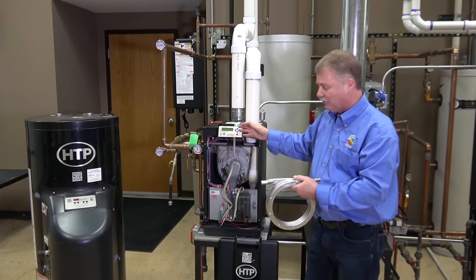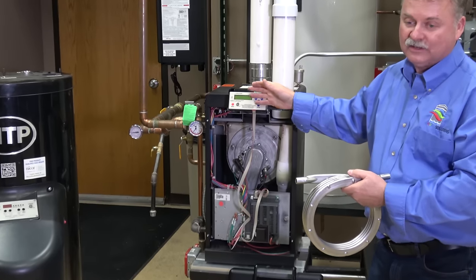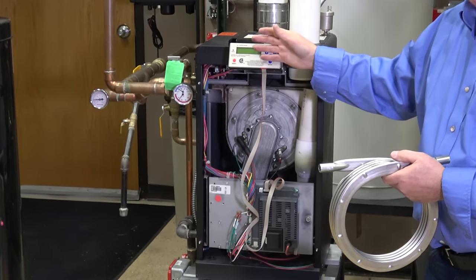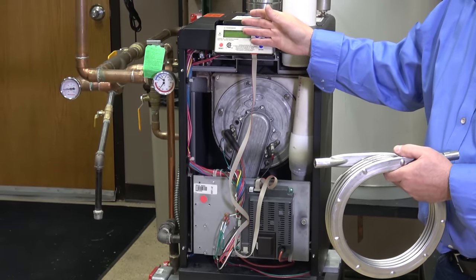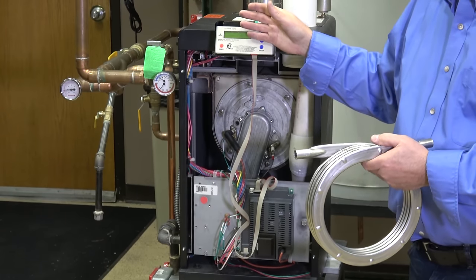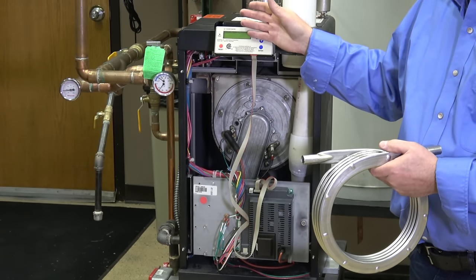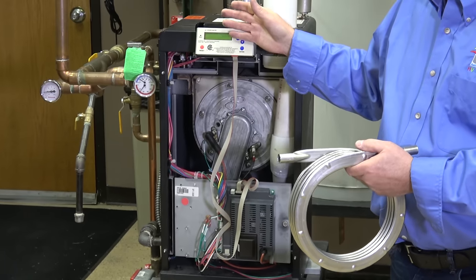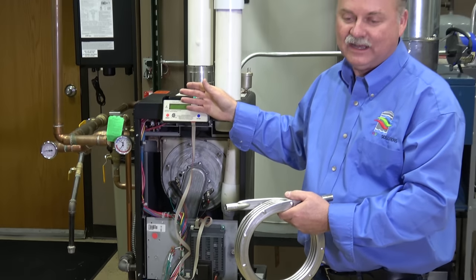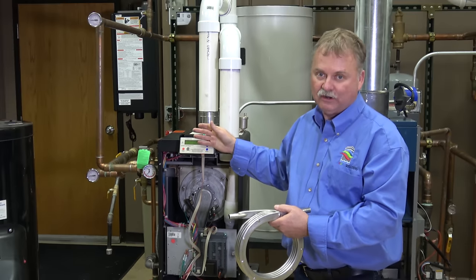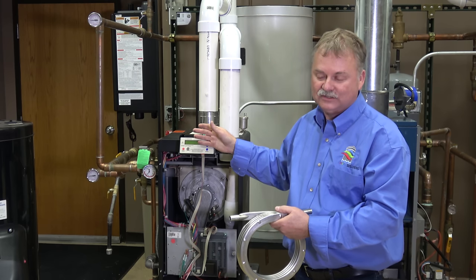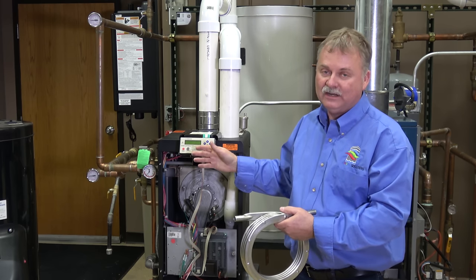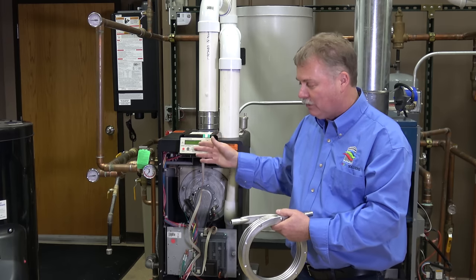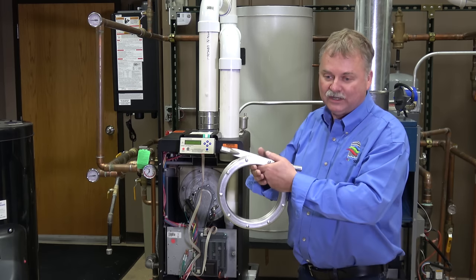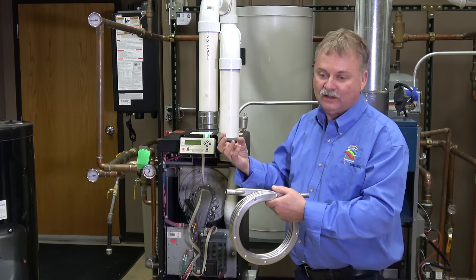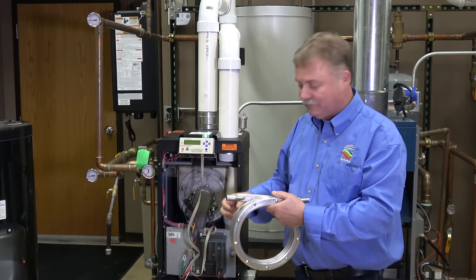A little bit different, you see a lot more controls here. It's basically a lot of readouts, a lot of stuff going on. There's a lot of programming. All these high efficiency boilers look at outdoor temperatures and work off of what are called reset curves. So on a day when it's 40 degrees outside and you don't need 130 degree or 150 degree water to heat your system, it might only make 110 degree water. The lower we can keep that water temperature, the more it condenses, the more fuel dollars you save.